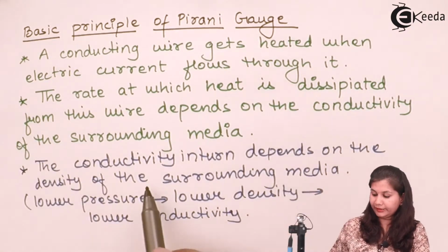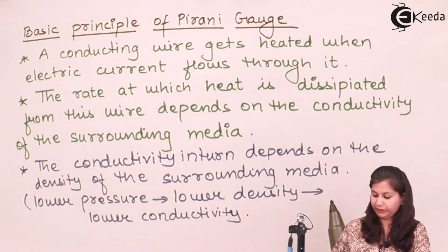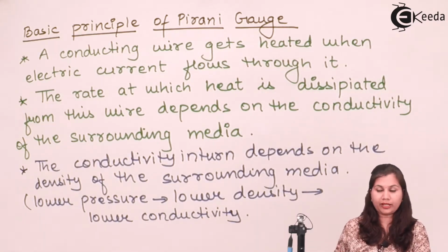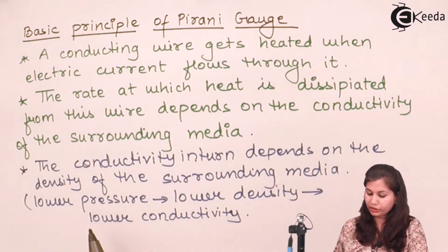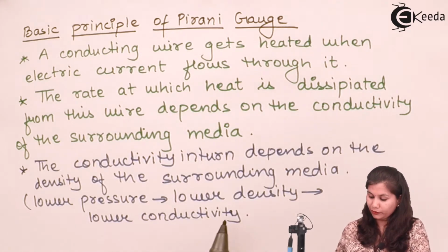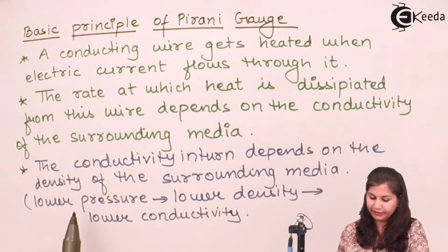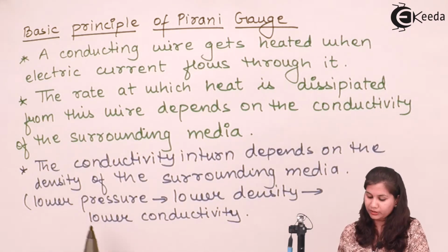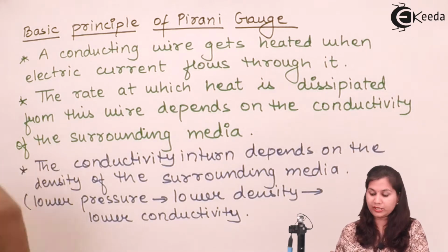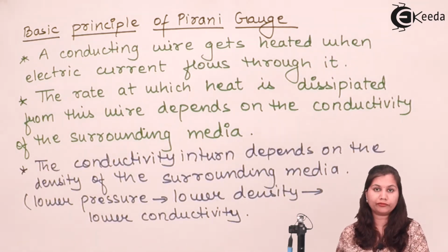Now, the conductivity, it depends upon the density of the surrounding media. Suppose that if the density of the surrounding media is less, then conductivity is less. Density means that pressure of the surrounding medium is less. So we can say that conductivity, indirectly it depends upon the pressure of the surrounding medium. So by measuring the conductivity, we can measure the pressure. So that is used in the Pirani gauges, that we are changing the conductivity of the wire, and by the change in the conductivity, we are measuring the pressure which is surrounding the wire.